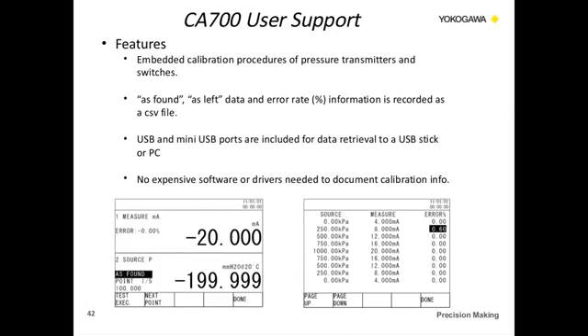So let's talk a little bit about the CA700 and some of the features embedded into the unit itself as far as the documentation part. The unit itself has embedded calibration procedures, and what I mean by that is you have the ability to save different calibration procedures there. So you can save a 3-step, a 5-step, 7-step, 9-step, a pressure switch calibration. You can save those, and then what that does is that saves time so that you don't have to go ahead and recreate that every time you want to calibrate a field device. The unit has the ability to do as found, as left. You also have the ability to enter in error data as far as a percentage, and all that information is saved as a CSV file, which is very easy to read. You don't need any expensive software for that. The unit itself, like I said, it comes with the USB and mini USB ports for retrieving that information.